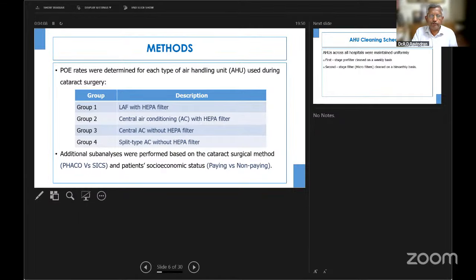We grouped the facilities into 4 groups: Group 1 is the 5 facilities with laminar airflow with HEPA filter. Group 2 had central air conditioning with HEPA filter but no laminar airflow. Group 3 is central air conditioning without HEPA filter, and group 4 has split AC.